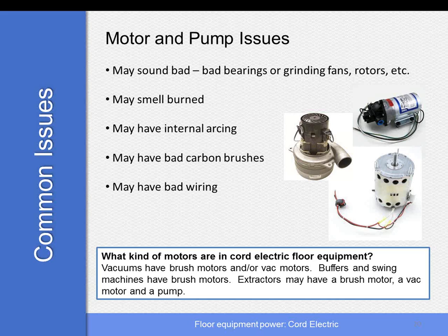Bad carbon brushes. Carbon brushes, which is a feature of a DC motor, they tend to wear. Actually, they're made to wear and made to be easily replaceable once they wear. They'll get to a spot where they don't make contact anymore, and you may look and see it looks like it's making contact, but there's just enough of an air gap between that carbon brush and the rotor or the armature where no electricity flows through and the motor just doesn't spin.